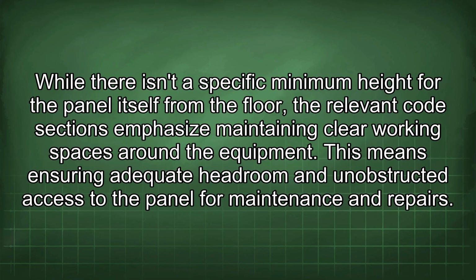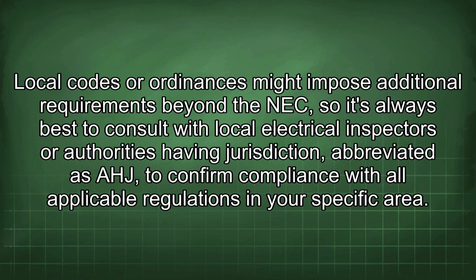While there isn't a specific minimum height for the panel itself from the floor, the relevant code sections emphasize maintaining clear working spaces around the equipment. This means ensuring adequate headroom and unobstructed access to the panel for maintenance and repairs. Local codes or ordinances might impose additional requirements beyond the NEC, so it's always best to consult with local electrical inspectors or authorities having jurisdiction, abbreviated as AHJ, to confirm compliance with all applicable regulations in your specific area.